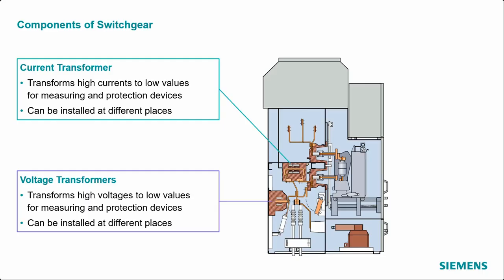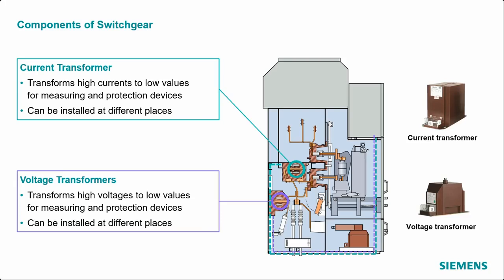They are usually wired to the low voltage box, where a protection device decides what to do when certain circumstances are met. For example, if there is a failure in one motor feeder, the current usually goes up in a certain way that is predictable. If the relay sees, using the information of the transformers, that the current is increasing in that known way, it understands that a failure is occurring and sends a trip signal to the circuit breaker. That way, the current is switched off before the motor gets damaged. This is why it's called protection. It prevents a serious failure from occurring.